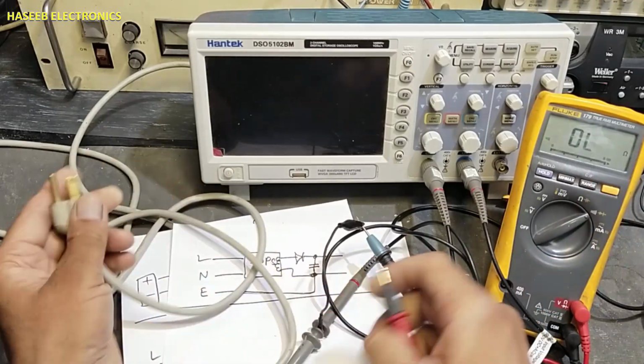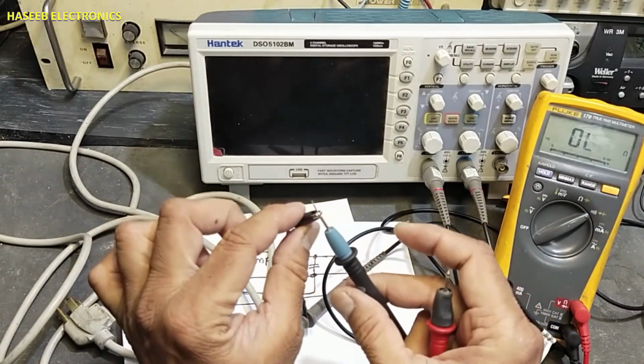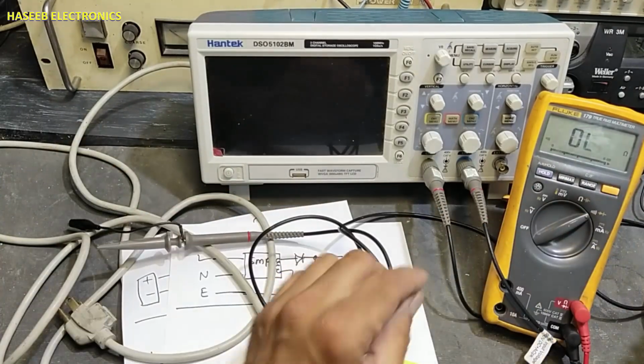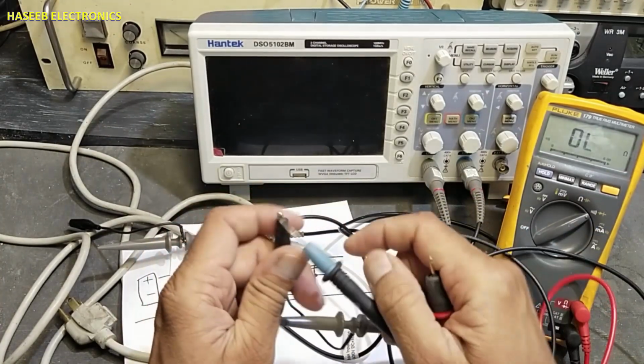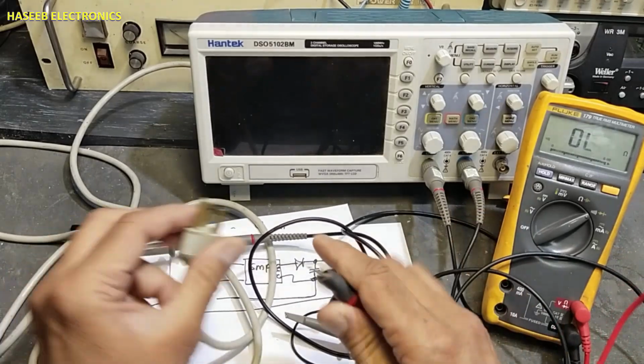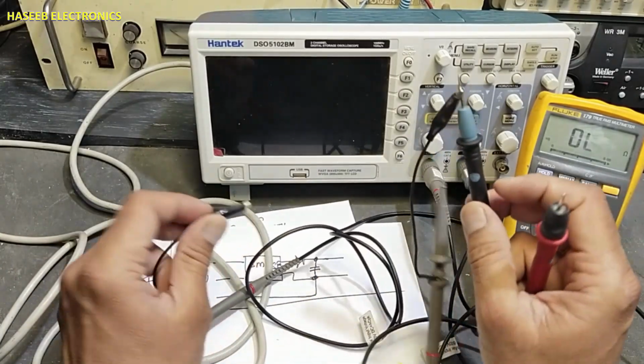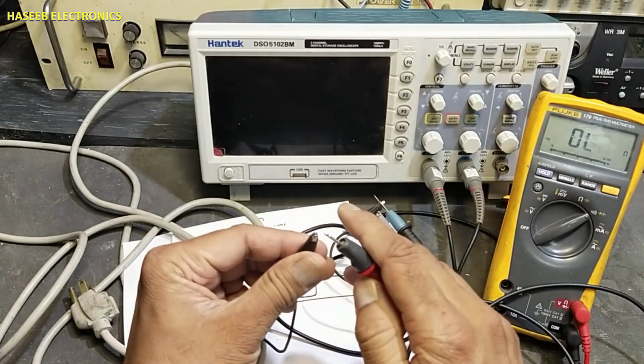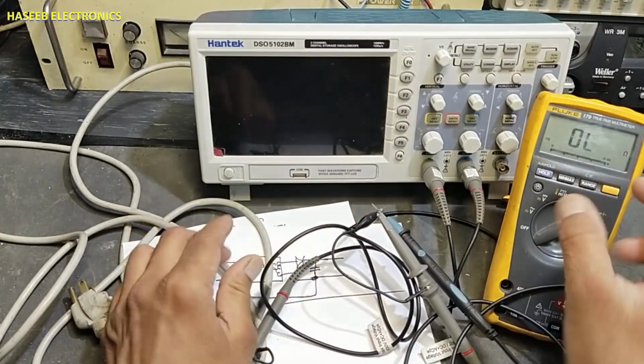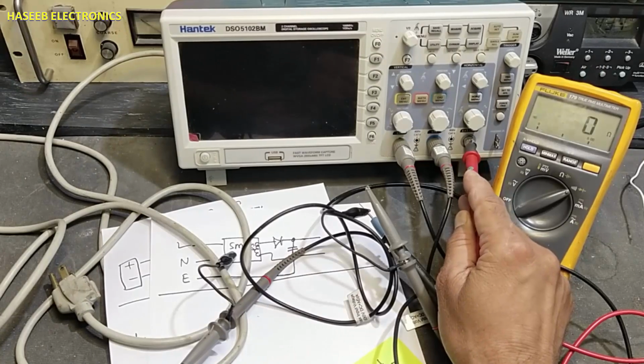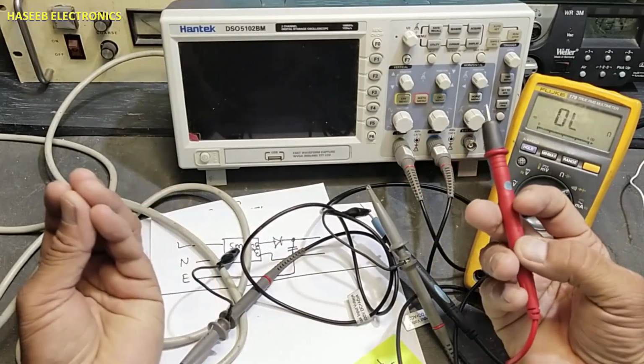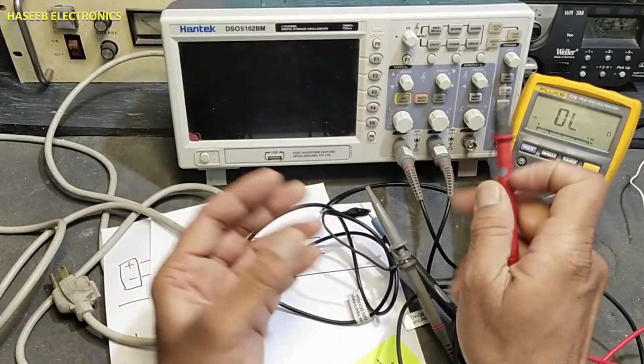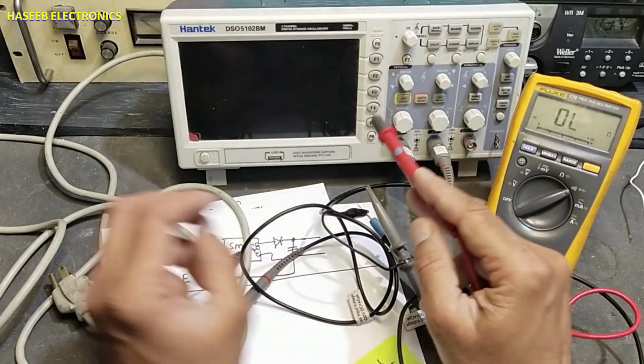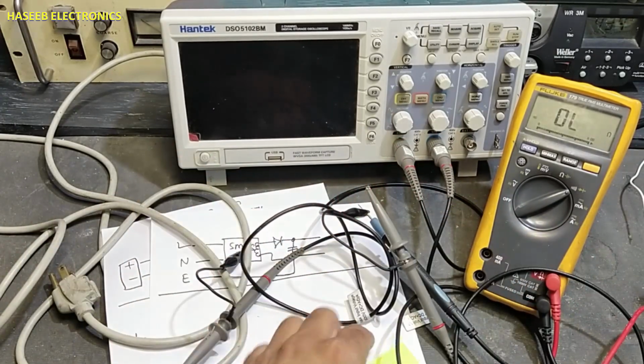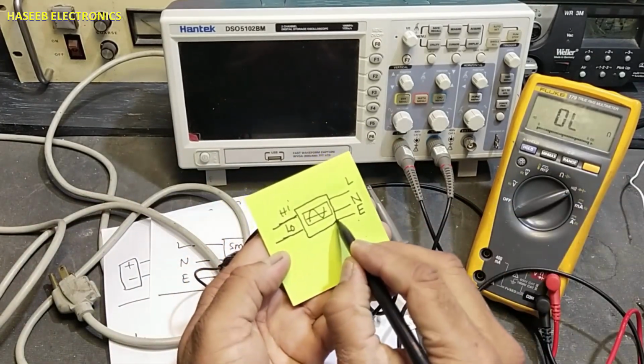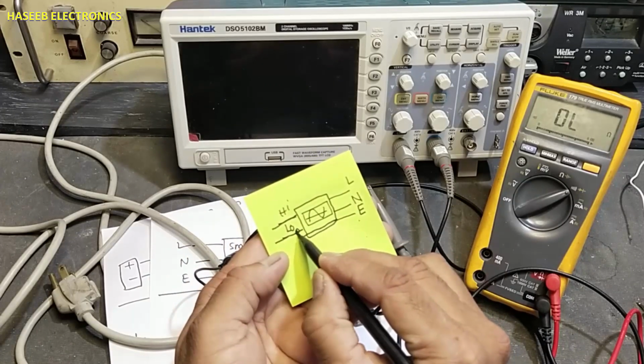So ground is directly coupled at the test probe. If we see the second probe, the same here. If we see the interconnection between this low and this low, it is the same. And if we see the trigger signal, if there is a sync signal, trigger signal, every signal, all these low sides are connected to the ground point. So these are connected internally to the low side.